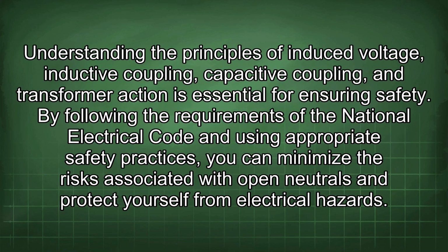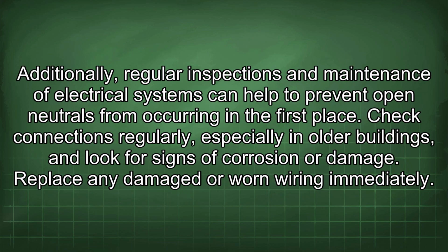Understanding the principles of induced voltage, inductive coupling, capacitive coupling, and transformer action is essential for ensuring safety. By following the requirements of the National Electrical Code and using appropriate safety practices, you can minimize the risks associated with open neutrals and protect yourself from electrical hazards. Additionally, regular inspections and maintenance of electrical systems can help to prevent open neutrals from occurring in the first place. Check connections regularly, especially in older buildings, and look for signs of corrosion or damage. Replace any damaged or worn wiring immediately.